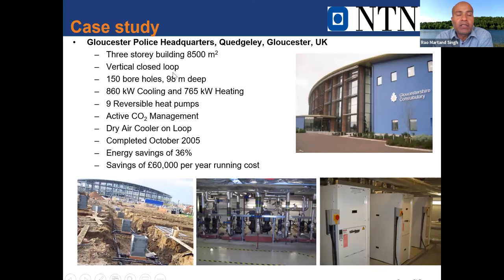Some examples of this technology, from when I was working in the UK. This is a police headquarters in Gloucester, using vertical closed loop boreholes, 150 boreholes going almost 100 meters deep. You can generally go up to 100 meters deep, sometimes 200 meters, depending on local geology and whether drilling is feasible or too expensive. If you hit rock, it can be expensive, so it's a trade-off between depth and drilling cost. This system was installed in 2005 and works very well, with good energy savings and monetary savings too.